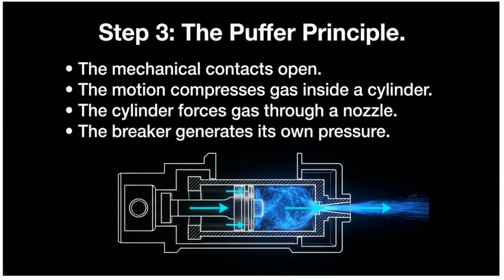Step 3 utilizes the puffer principle. As mechanical contacts open, the motion compresses gas inside a cylinder. The cylinder then forces gas through a nozzle, allowing the breaker to generate its own pressure.